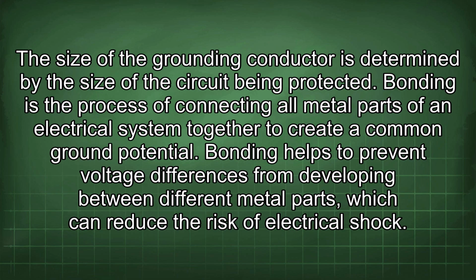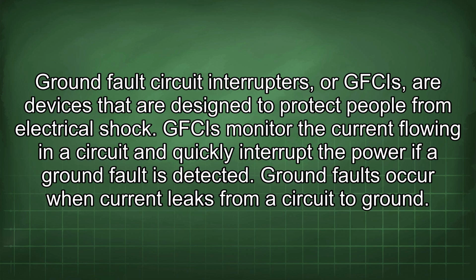Bonding is the process of connecting all metal parts of an electrical system together to create a common ground potential. Bonding helps to prevent voltage differences from developing between different metal parts, which can reduce the risk of electrical shock. Ground fault circuit interrupters, or GFCIs, are devices that are designed to protect people from electrical shock. GFCIs monitor the current flowing in a circuit and quickly interrupt the power if a ground fault is detected. Ground faults occur when current leaks from a circuit to ground.